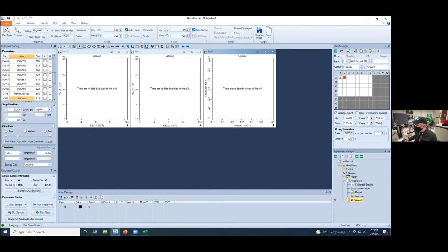At this point, we are ready to run the plate. As I said before, I'm not going to worry too much about the gain at this point. The detectors have such a high dynamic range that it's very unlikely that I'll saturate my detectors. So for pretty simple experiments, I'm going to go with the starting gains. If you start having very complex experiments and you want to manage your spectral overlap, you might want to revisit those gains. But for now, this is going to work quite well.